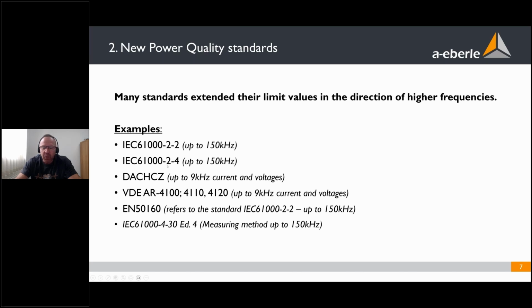The next standard, which is coming this year, is an international standard for industrial areas, the 61000-2-4, and also here you will find in future limits up to 150 kilohertz. So it is necessary that the analyzer also measures up to 150 kilohertz. And then you find national and international, many other standards that extend the limits to higher frequency ranges.